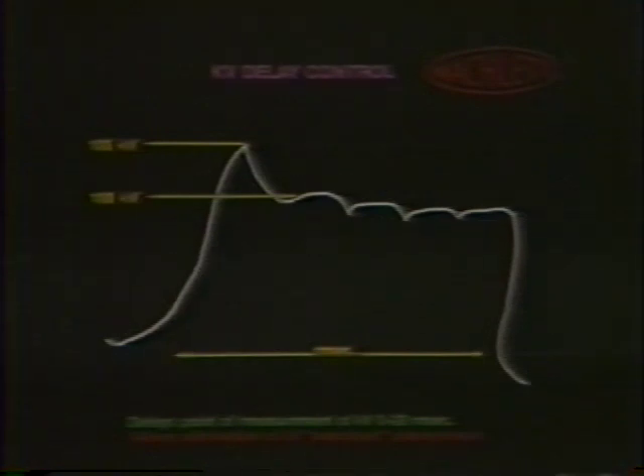Most three-phase generators have a leading-edge overshoot, as shown on this slide. The kV delay control can delay the point of measurement out 20 milliseconds to determine if that is in fact the case. You'll note that we have the 100 kV set into the generator. We very likely would be getting 105 kV read on the display. We then turn the knob out to 20 milliseconds, and we can have a look that far out and note that it's 100 kV and understand what our problem is.